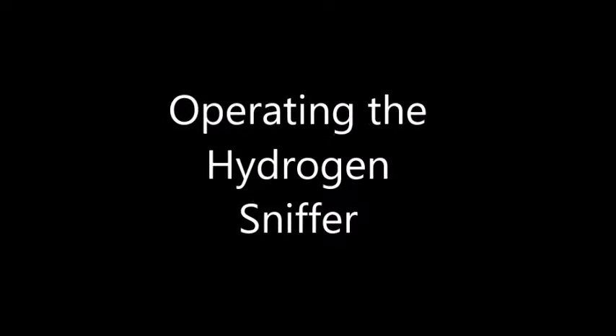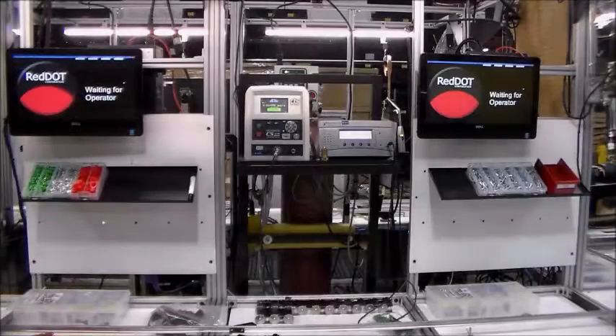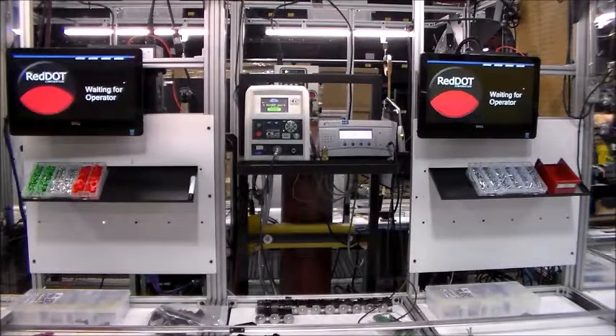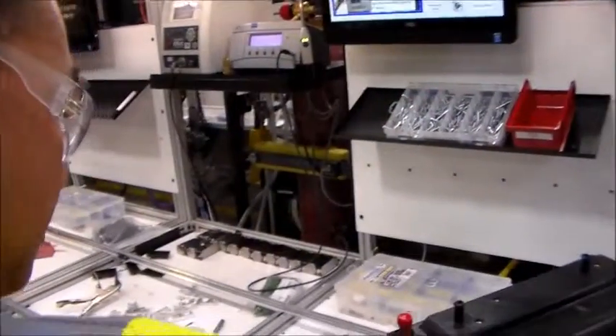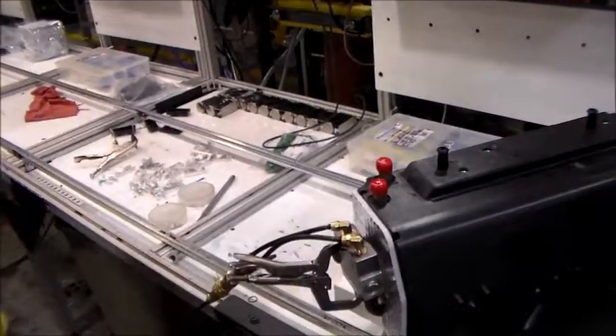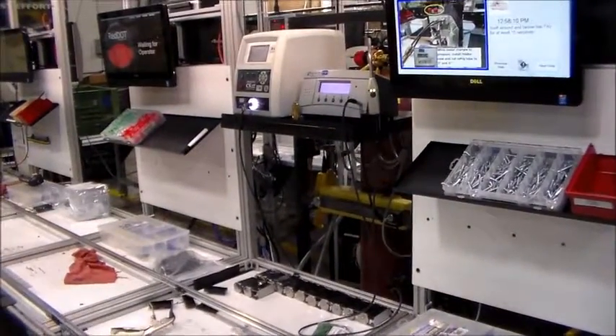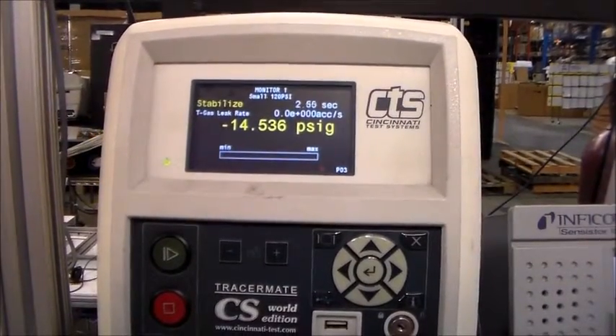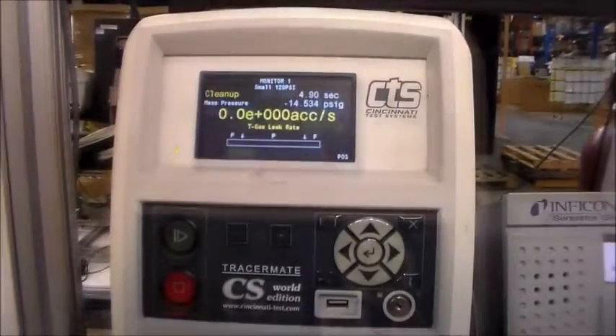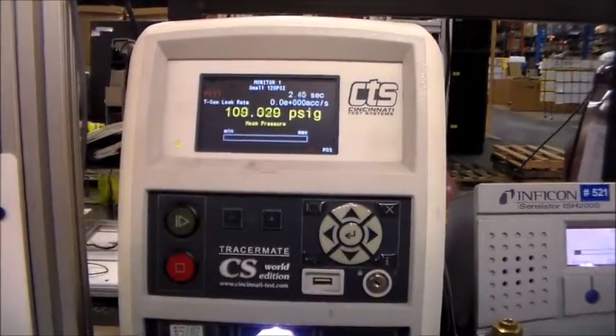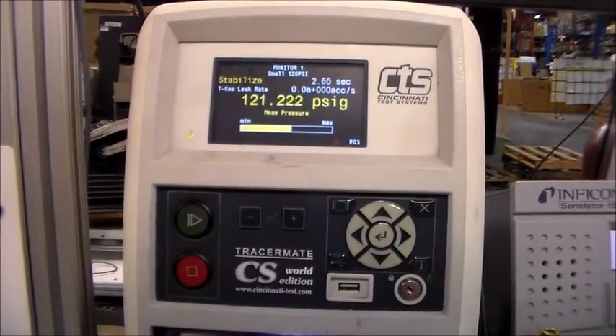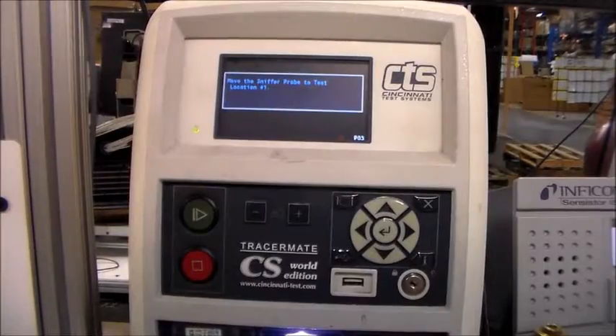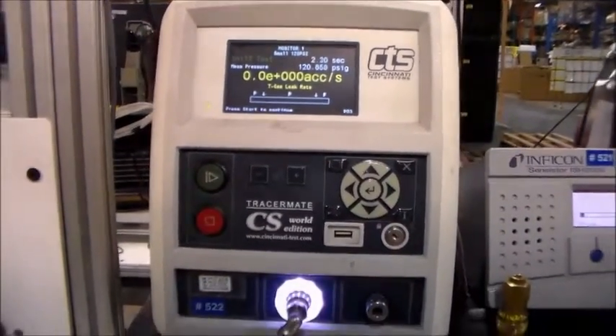Now, let's go over the normal operating procedure for the hydrogen sniffer. Start by having the ISH 2000, the tracer mate CS, and vacuum pump all turned on, and verify the settings from the machine setup section are correct. Connect the part to be tested to the machine using the correct clamp for that unit. Press the green Start button. The tracer mate will evacuate the part of air, then test the vacuum of air. Once the vacuum is stable, the part is filled with the tracer gas, and that pressure is stabilized. When these phases are complete, the LED light ring on the tracer mate will flash white, indicating the tester is ready to sniff the part.